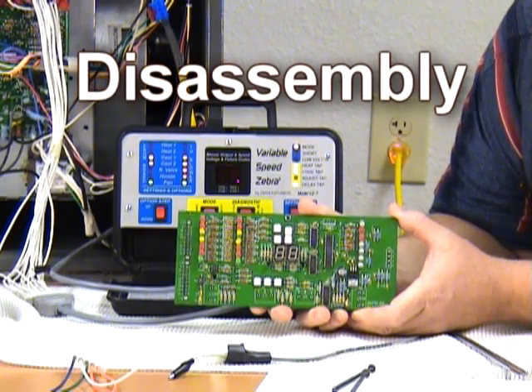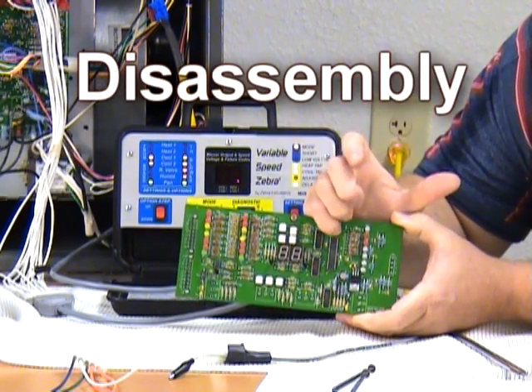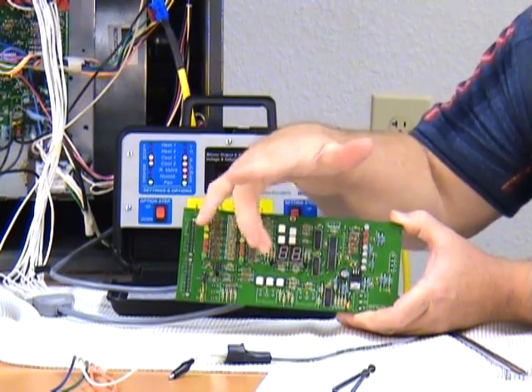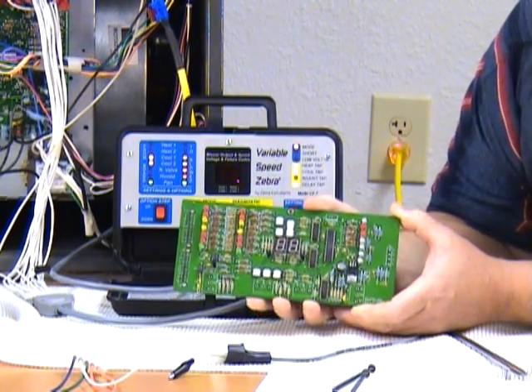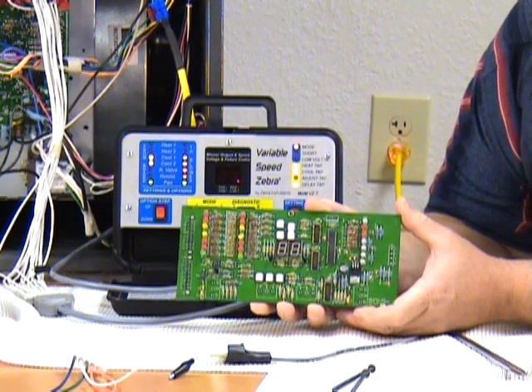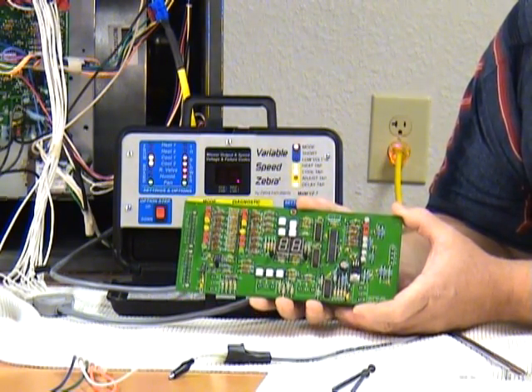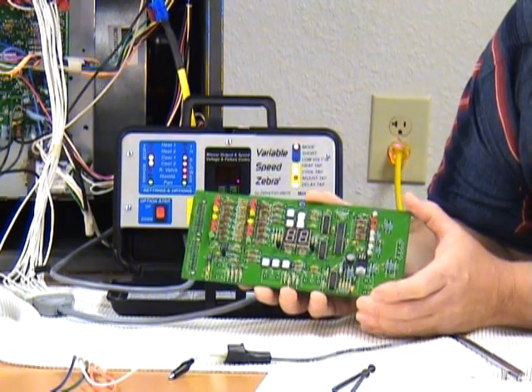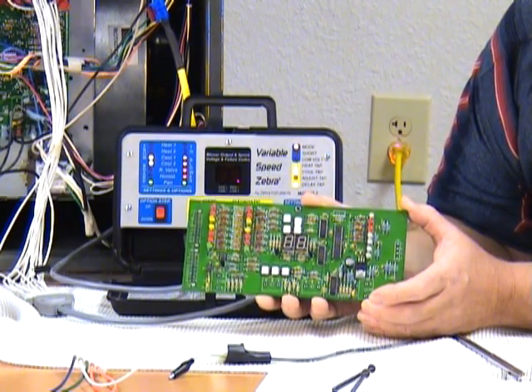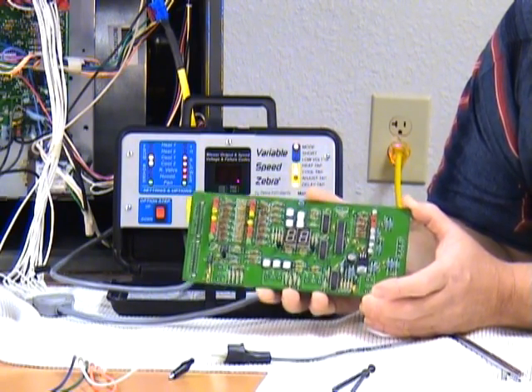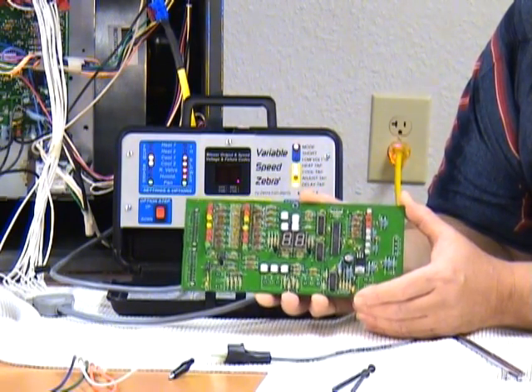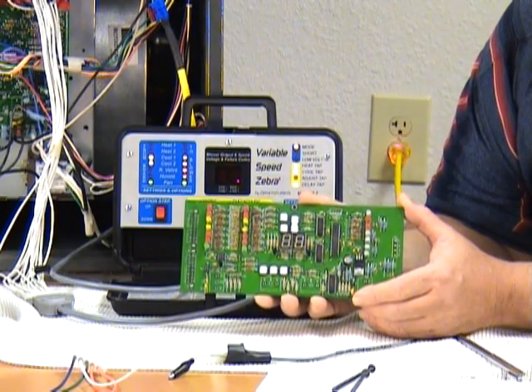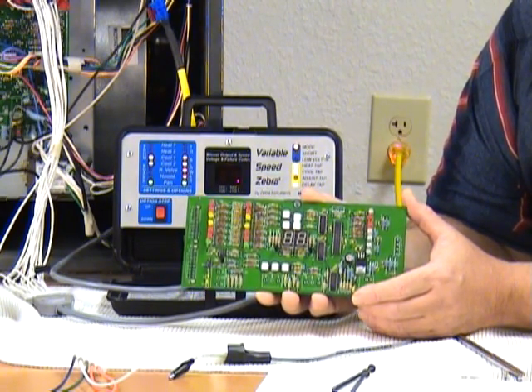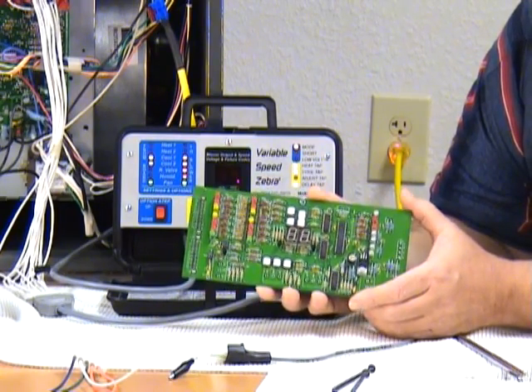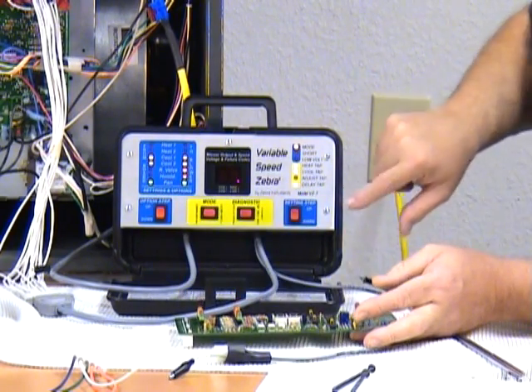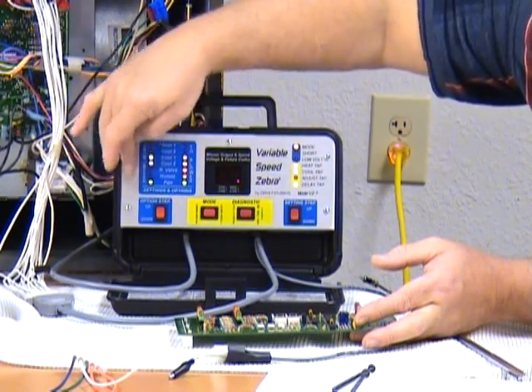This is the circuit board that's inside the variable speed zebra. There's a small microprocessor along with a number of other integrated circuit chips that process the signal circuitry that goes into and out of the variable speed zebra. As you can probably guess by seeing computer parts in there, you understand what happens if it gets wet. Don't let the inside of your variable speed zebra ever see moisture. If you do, you got to make sure it's completely dry before you let it run again. We don't recommend you ever take it apart, but if you do have to take your variable speed zebra apart, these 4 screws are not the proper way to take it apart.